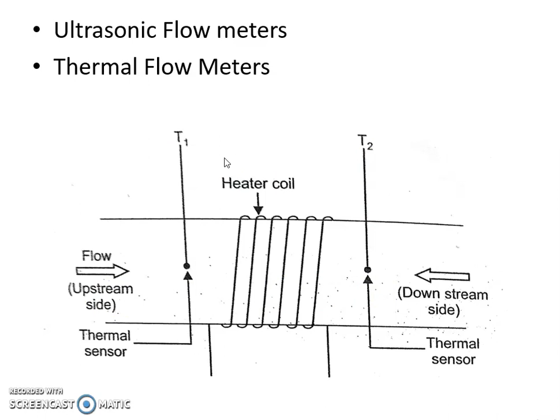Now when the fluid is flowing and the flow increases, the temperature T1 will decrease and the temperature T2 increases until the steady state is reached. As the velocity of the fluid increases, T1 goes on decreasing and T2 goes on increasing. Therefore the difference in temperatures, T2 minus T1, will be more as the velocity of the fluid is increased. So in this case the fluid velocity is measured in terms of the difference in the two temperatures, T2 minus T1. So in this way thermal flow meters are used to measure the fluid flow velocity.